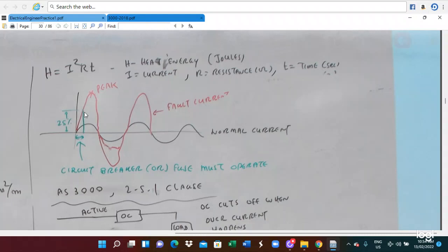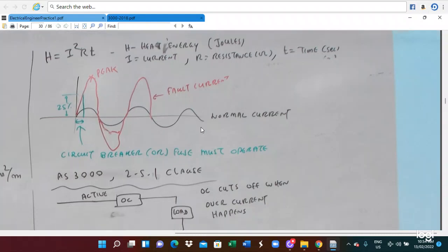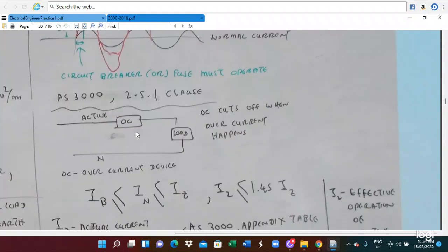Therefore, this is very important. When we are setting the appropriate protective equipment, before reaching the peak point, when about 25% of the peak is reached, at that time the circuit breaker must operate. So this is the way we protect the circuit. So circuit breaker setting is an important aspect.